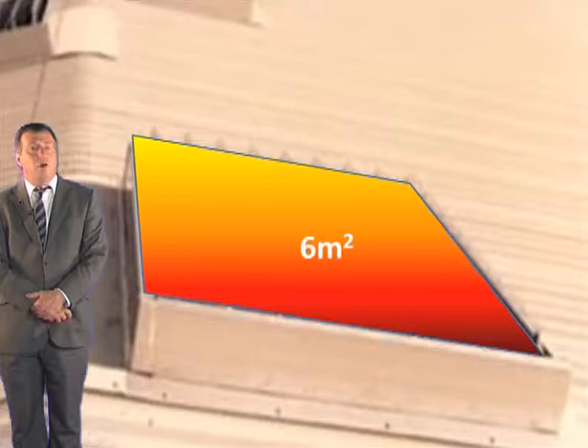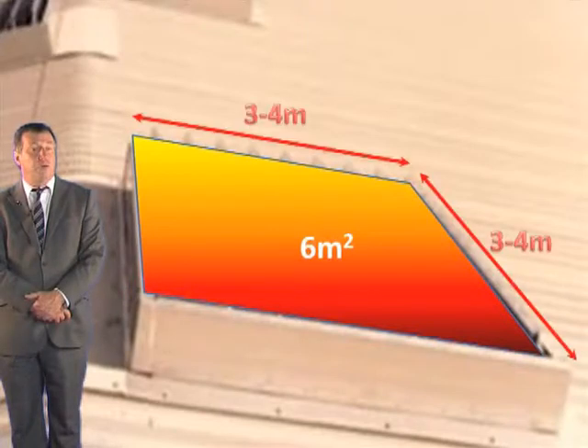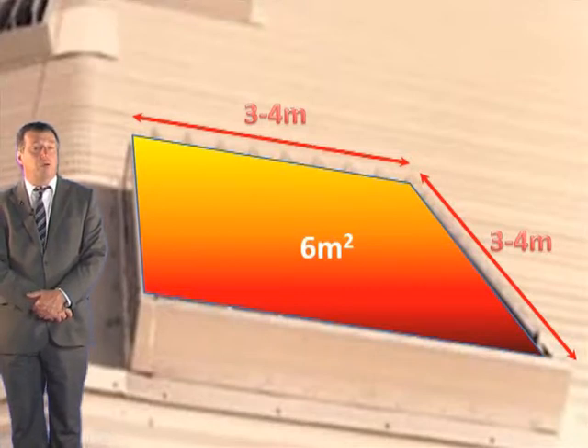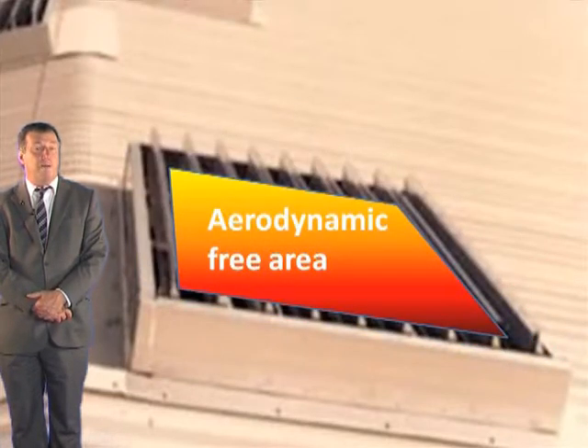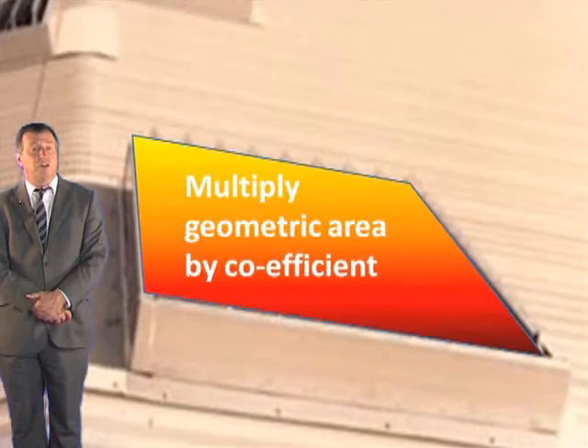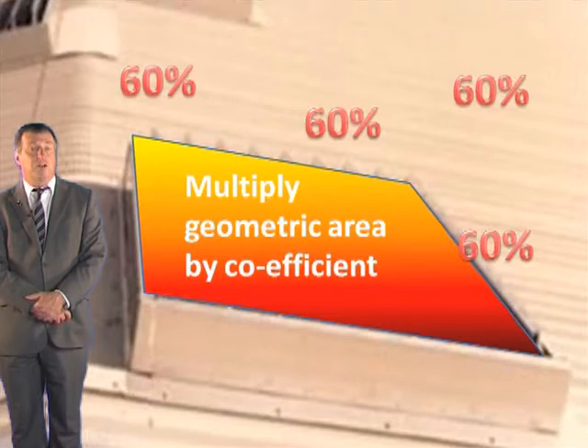So how big are ventilators? Well, they're not normally larger than about 6 square metres in geometric area, with dimensions not normally exceeding 3 or 4 metres in either direction. As mentioned earlier, to determine the effective area of a vent, otherwise called the aerodynamic free area, it's necessary to multiply the geometric area by the coefficient of ventilation, which is usually about 0.6 or 60%.